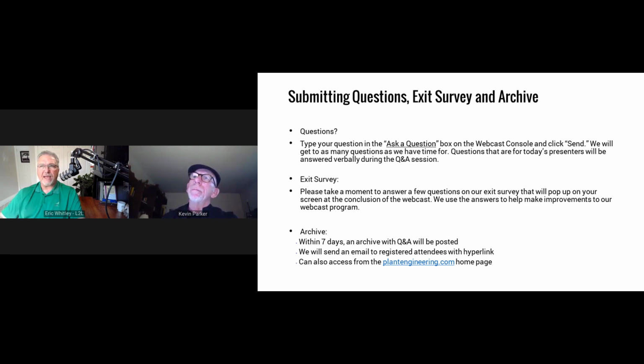Another big mistake that just popped into my head is people's inability, or lack of systems, processes, or protocols, to make adjustments to the cycles when a failure happens. So if a failure happens on third shift, and somebody goes out and changes something out and that doesn't get documented, listen, that's a failure that needs to be factored into the cycle count. We're doing a PM every 25,000, but we had a failure at 18,000 and nobody documented that, so we are way over on our cycle count. We need to be able to make those adjustments as well. So that's the other thing, just not being able to capture and make adjustments to the actual cycles.